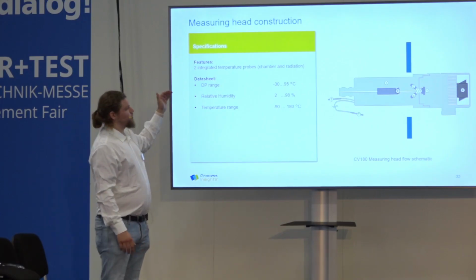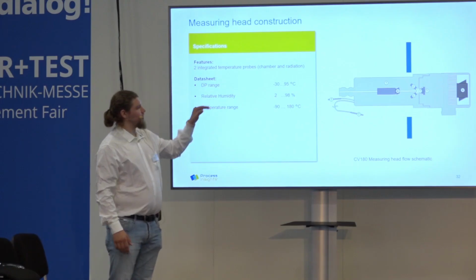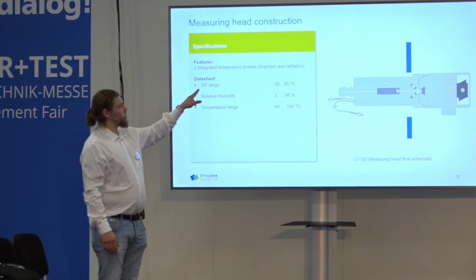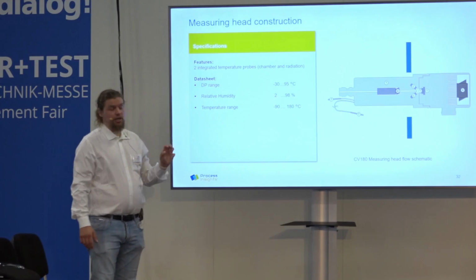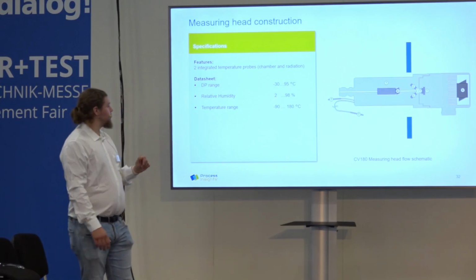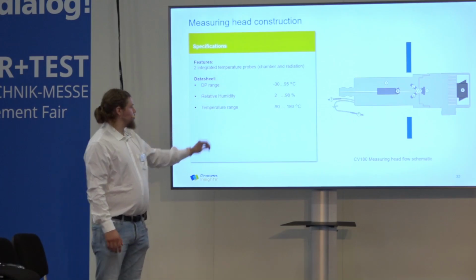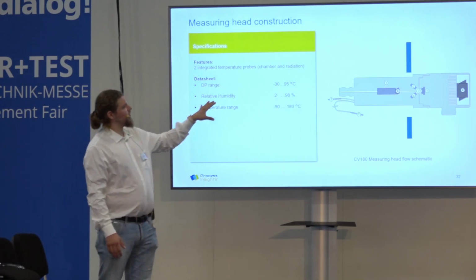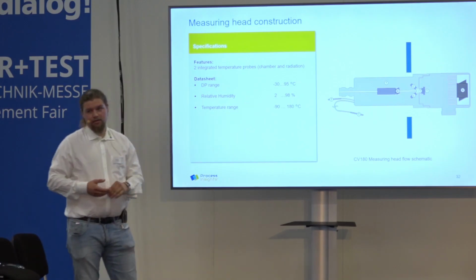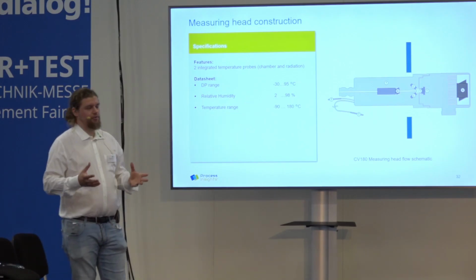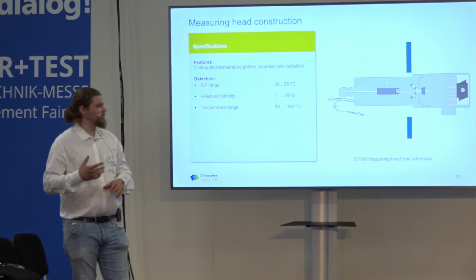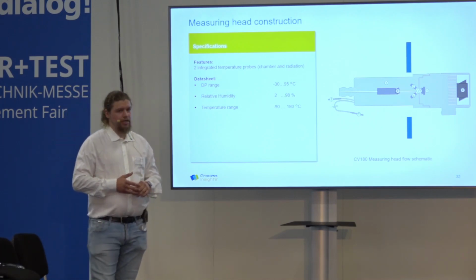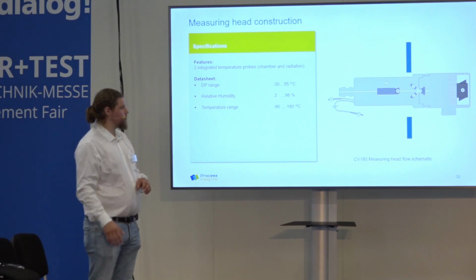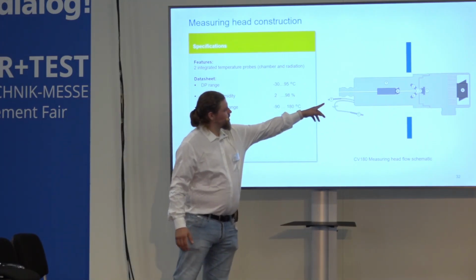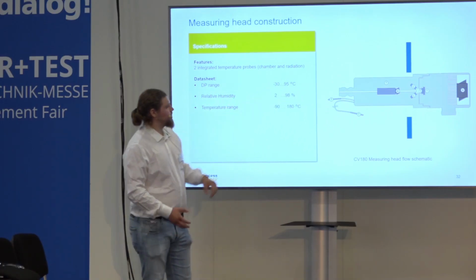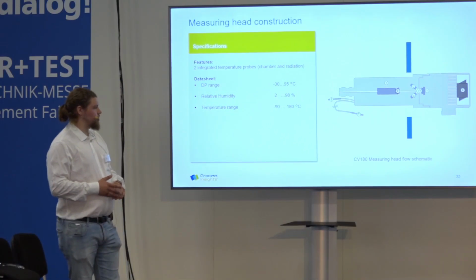And the range which we can measure is a dew point from -30 to 95 degrees Celsius. If we go for frost point in the specifications, we define it by -27. And relative humidity from 2 to 98%. And temperature based on the type of CV180, there are two types. The one type is for the full climate chamber calibration, and the other one is called CV180 ST2. It will have only two temperature probes, which will then represent the chamber temperature and one for radiation correction. So you will have then only two temperature probes.